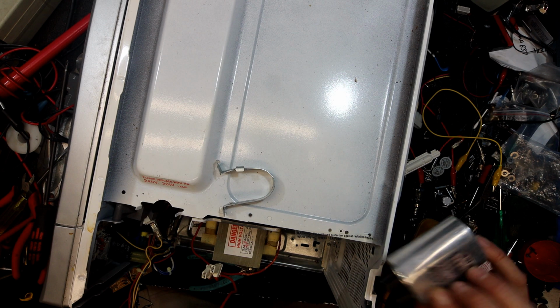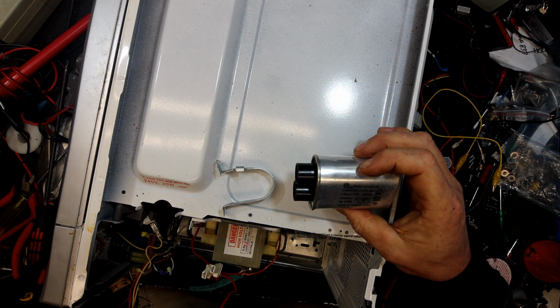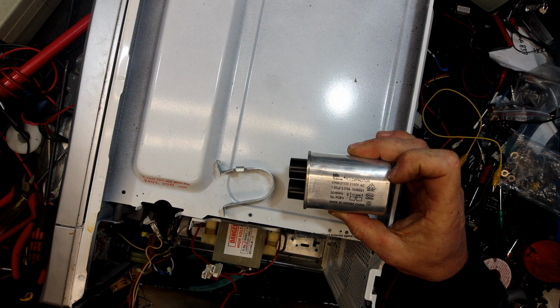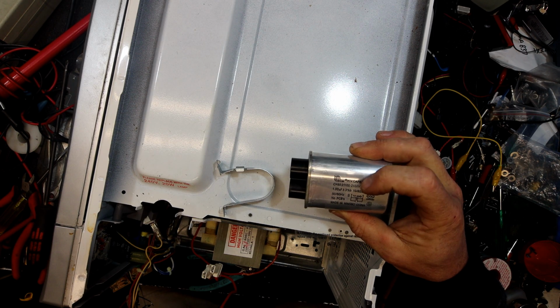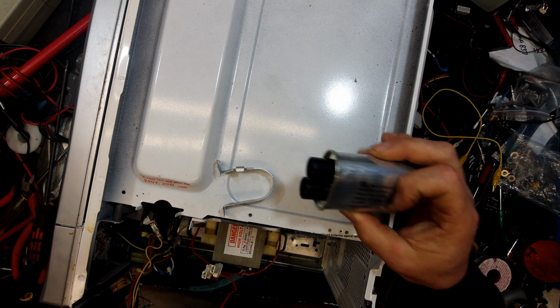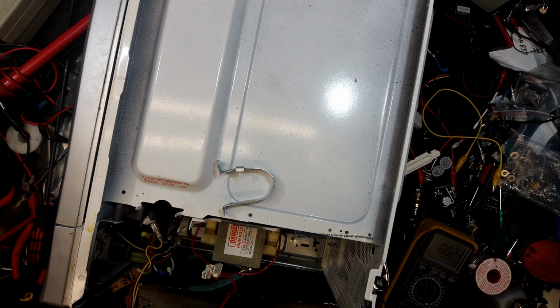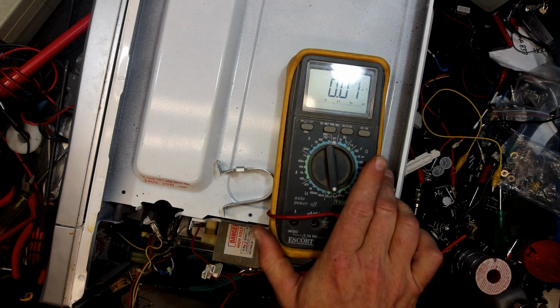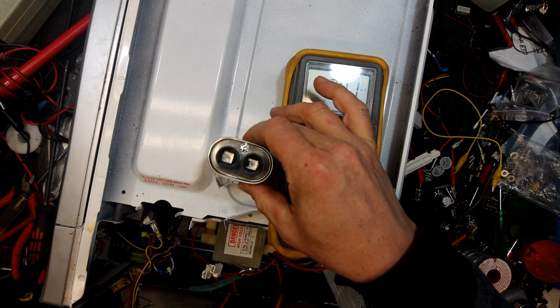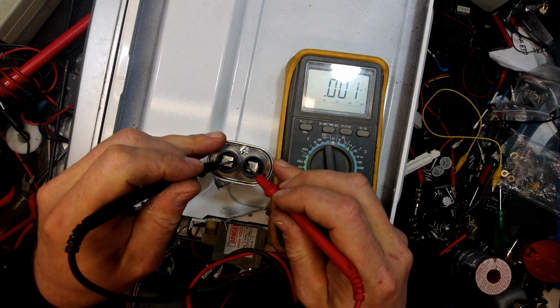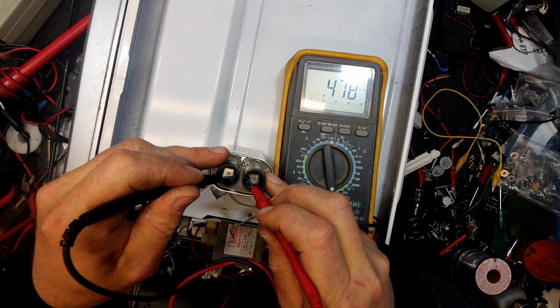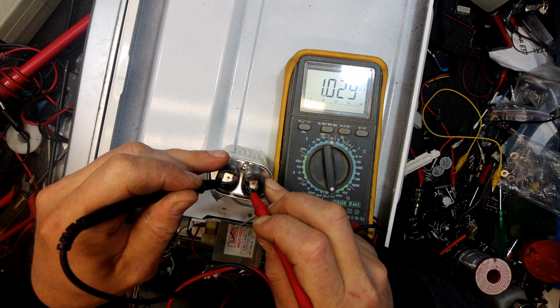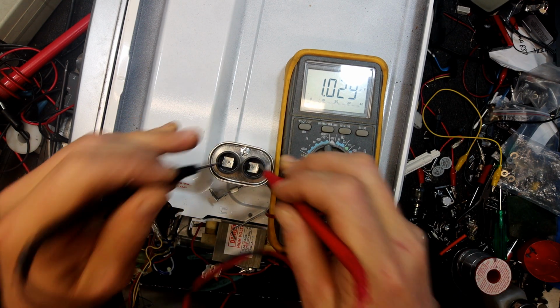What do we got, 1 microfarad at, yeah, should be 2100 volts, so they run a bit below that. This actually had, how much voltage? We had 27 across there, so this was technically exceeding its ratings. Let's go to the 4 microfarad range and see what we get, if anything. Right on 1 microfarad, so I'll say that'd be fine.